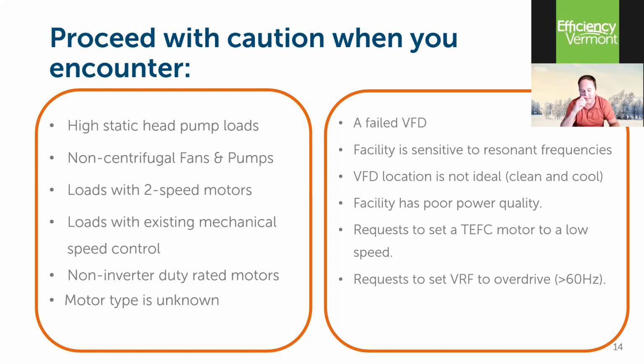Request to set a totally enclosed fan cooled motor to a low speed. There is a certain minimum speed for certain motors that has to be maintained for cooling purposes. So those are motors that you wouldn't necessarily want to run at 10 hertz because the heat buildup would be detrimental to the motor. So just another moment to pause and question which type of motor you have.